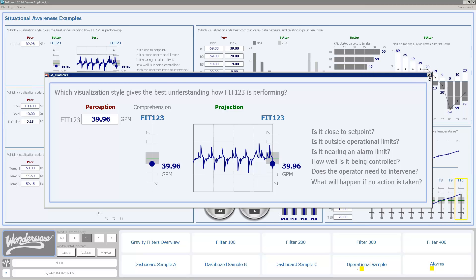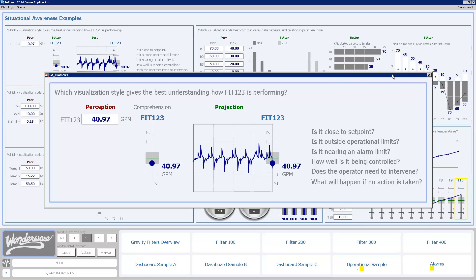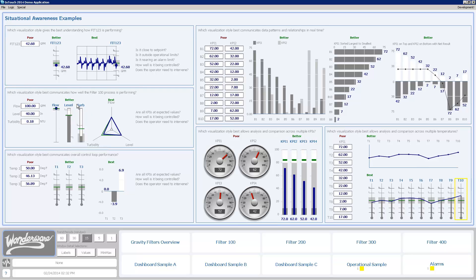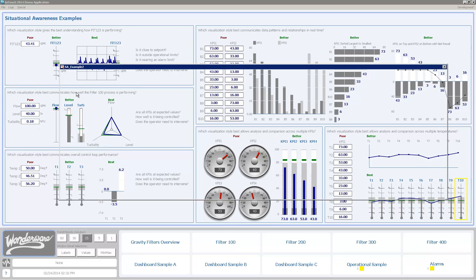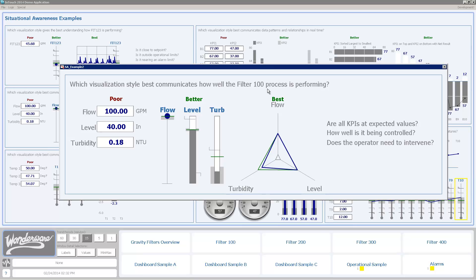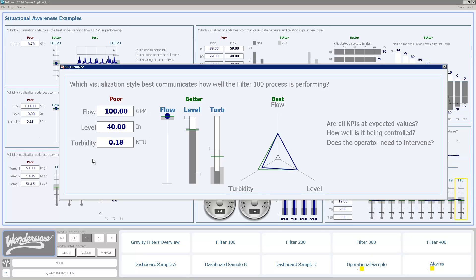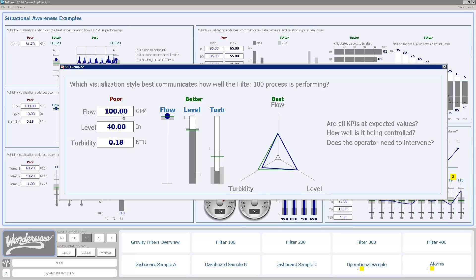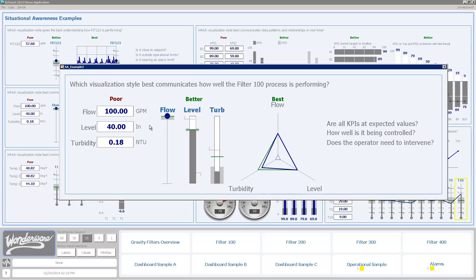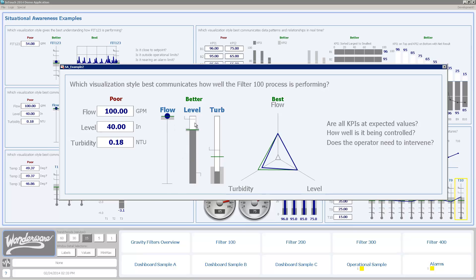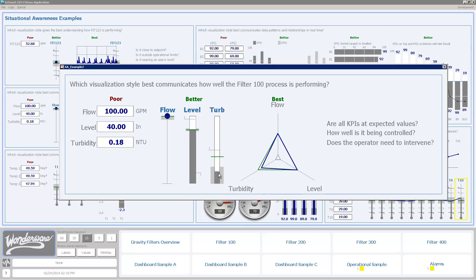I'm now going to move on to my second example here, where I've got three variables which are key indicators for a process: a flow, a level, and a turbidity. Turbidity is a measure of clarity of water. So this is a water filter and I want to know how well am I doing. The first way of indicating it, just using numeric values, the classic way of tag name, numeric value, and engineering units, don't really tell me how well I'm doing. When I use these meters here in the middle I get a little bit better. I can see that my flow is right on set point, my level is on set point, my turbidity is still pretty low, so I'm doing pretty good here.